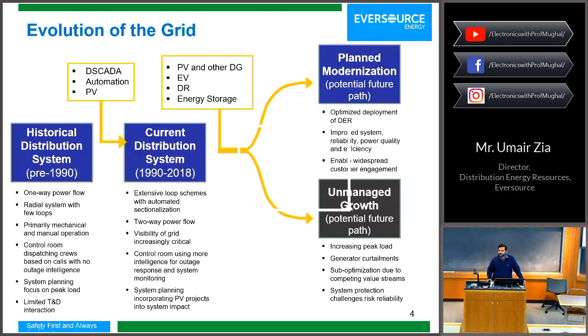When an outage happened in the past, first off we would not have any idea because there weren't enough sensors on the system to know exactly who lost power. So we relied on end users calling the utility to say they lost power. Then a manual troubleshooting sequence took place where an actual person went out with a utility truck to try to find where the outage happened.